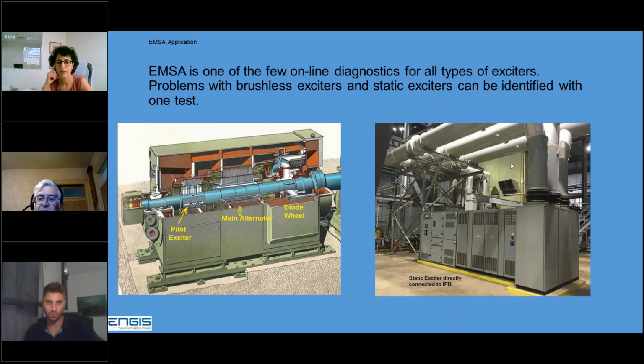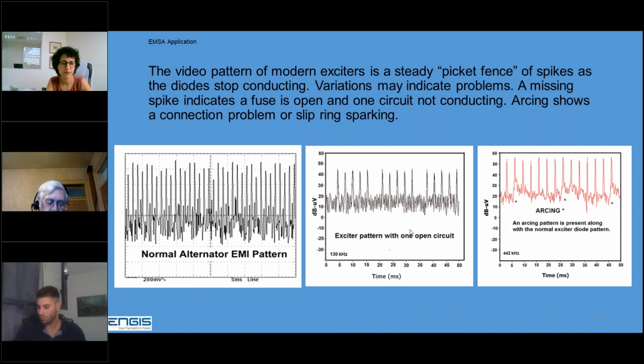Static exciters, the big ones, are fed directly from the isolated phase bus. They'll have a transformer cubicle, and then the rectifiers, and then the control unit. And all of this can be scanned with the sniffer. The pattern that we see, the video pattern, as I say, looks like a picket fence, a lot of spikes. And this is caused when the diodes turn off and stop conducting, they usually chop current. So they oscillate a little bit and they produce a radio frequency. They produce EMI.